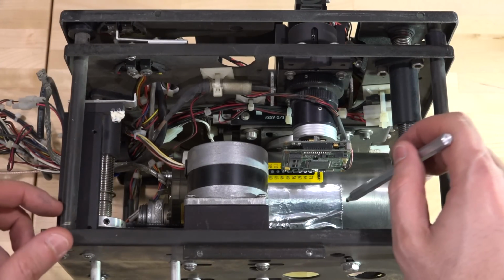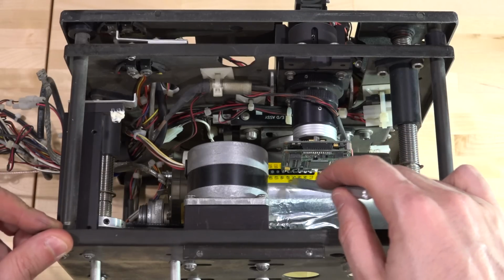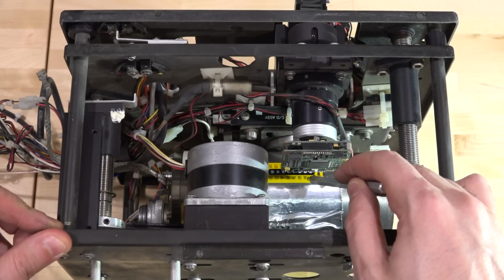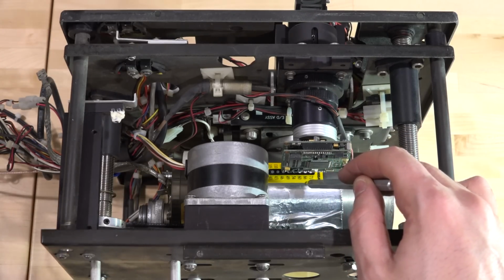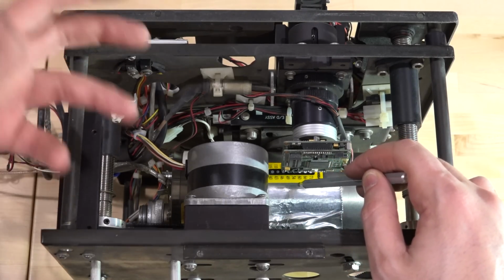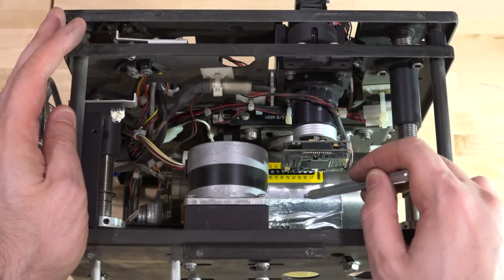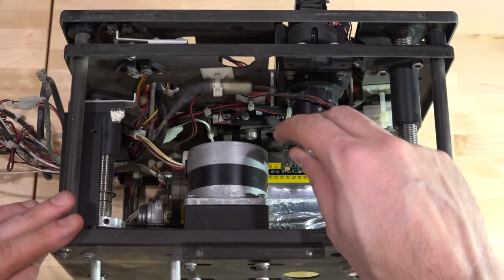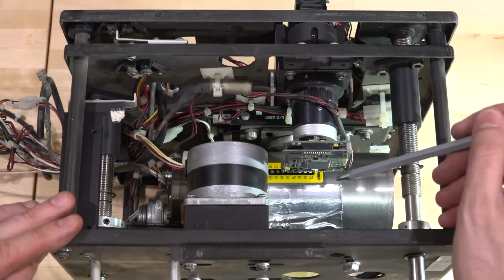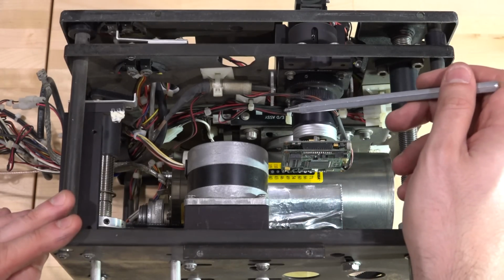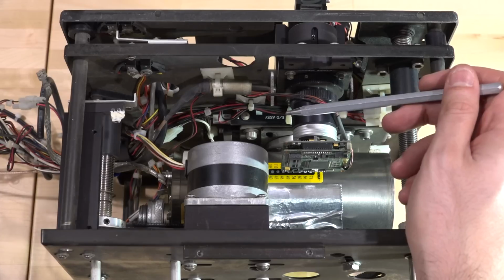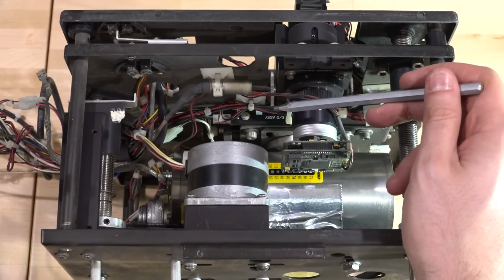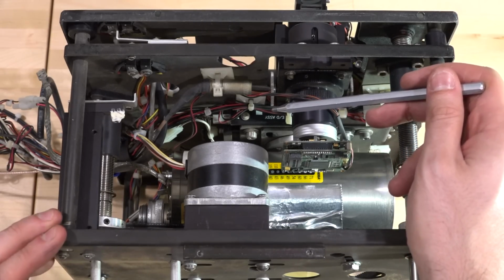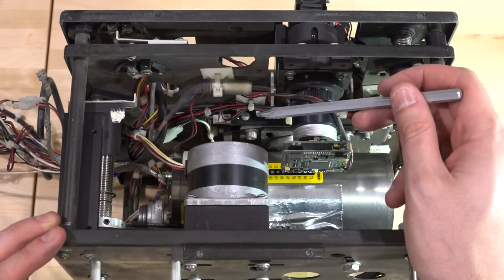The rest of it at the bottom here, this is our main X-ray tube, and on there is a thermochromic little thermometer attached to it that changes color depending on the temperature. It must be just something for diagnostics, but you can't see this from the outside. Anyway, now right underneath that, that thing over there, is in the way of the X-ray output on the other side, and it's a shutter, and I think it's basically an X-ray shutter. I've never seen one of those before, but I wonder why it is there, or perhaps it serves some other purpose that I can't figure out quite yet.